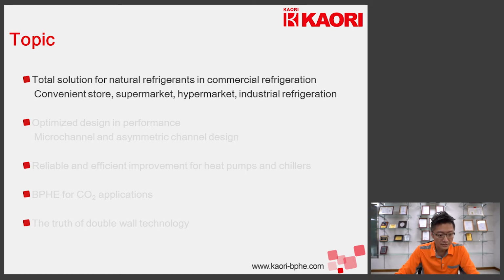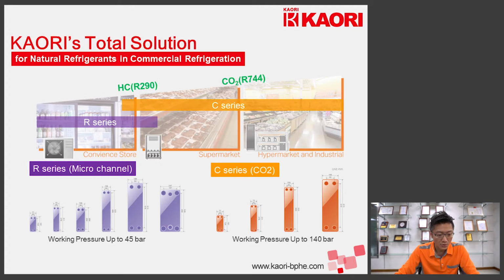So the most common natural refrigerants in the commercial refrigeration are propane and CO2. And let's talk about how KAORI's brazed plate heat exchanger can be utilized on both natural refrigerants. KAORI offers total solution for commercial refrigeration, as convenience stores and supermarkets are in every corner of our lives. Imagine if we replace all refrigerants by natural refrigerants. This will make a huge difference in our environment. Because propane is a very flammable gas, its usage amount must be limited.